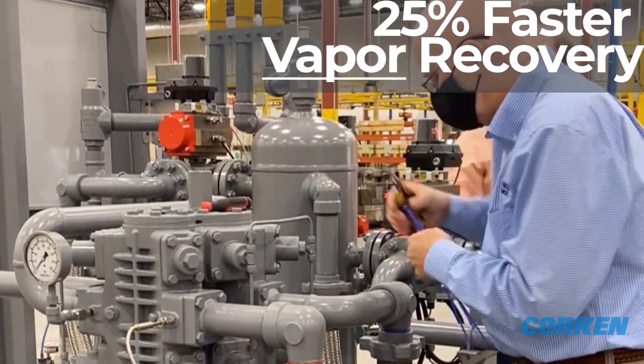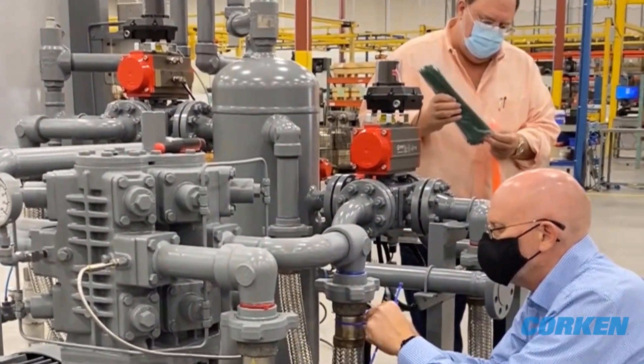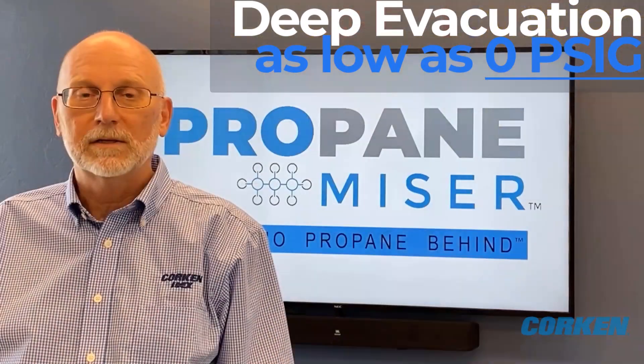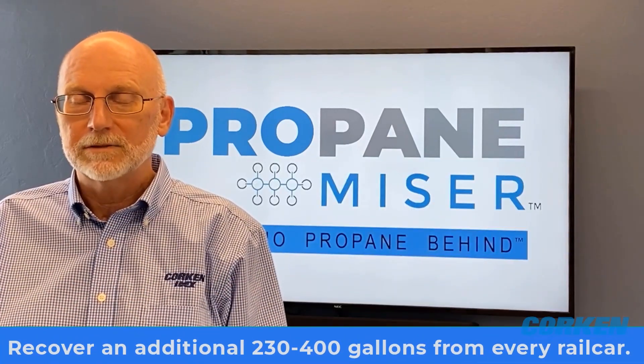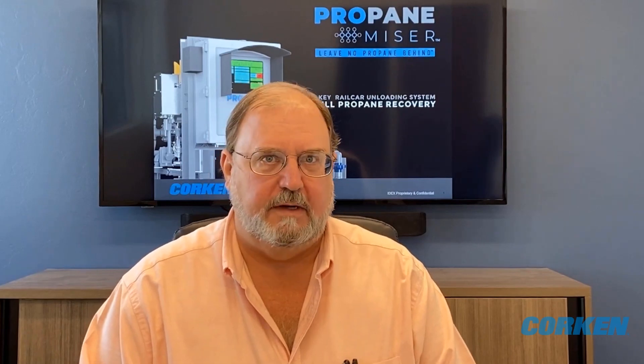Number three is fast vapor recovery. The Propane Miser recovers vapors 25% faster than the current high capacity compressor on the market. Number four is deep evacuation. You can recover the contents of a rail car as low as zero PSIG and recover an additional 230 to 400 gallons out of every rail car you unload.